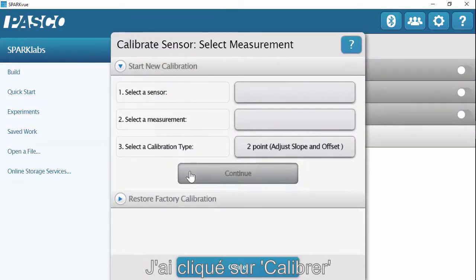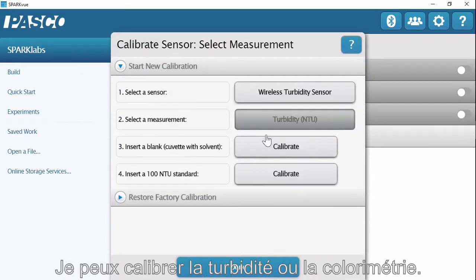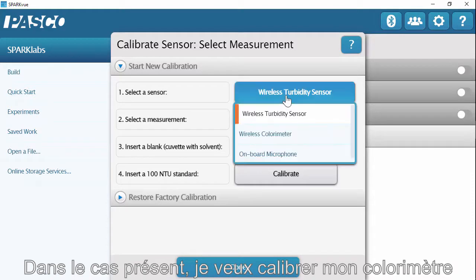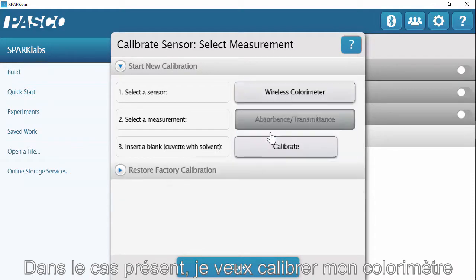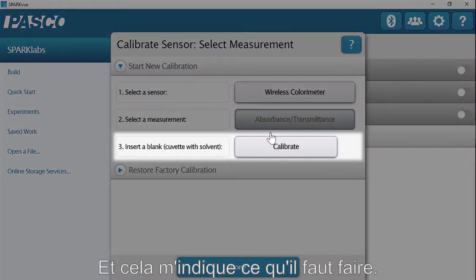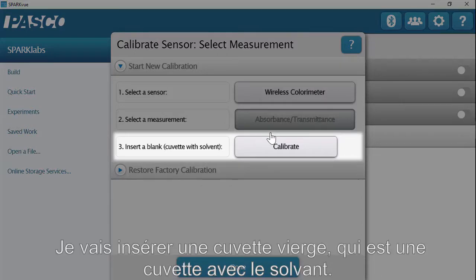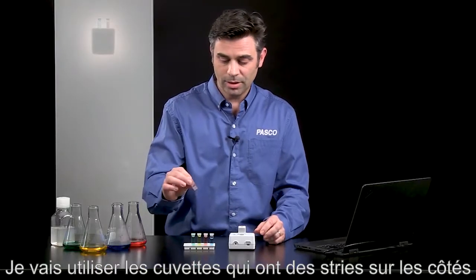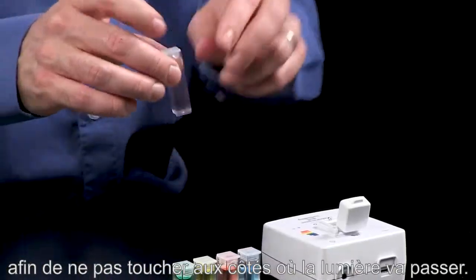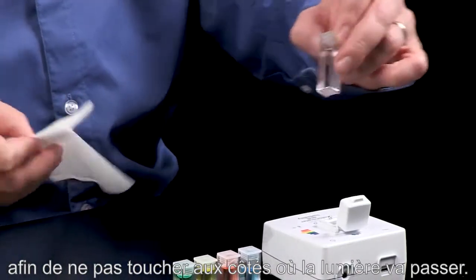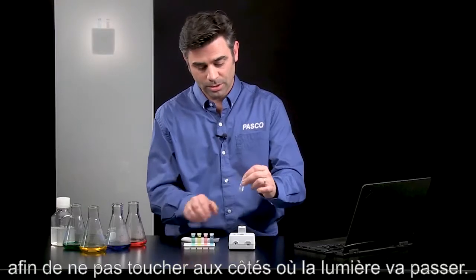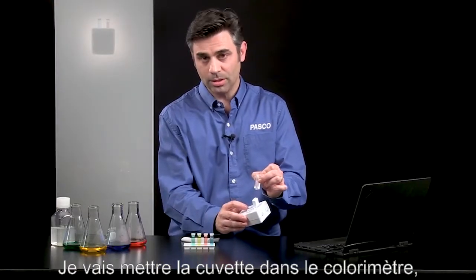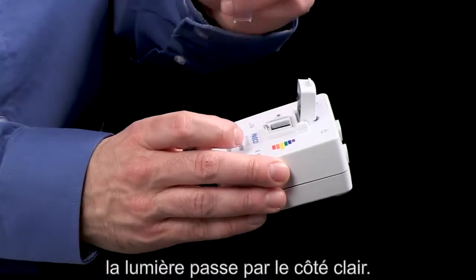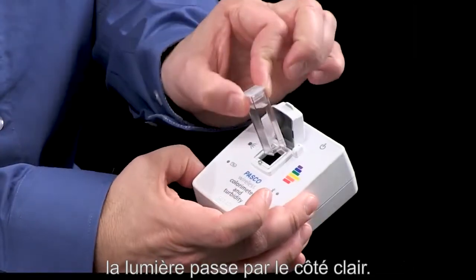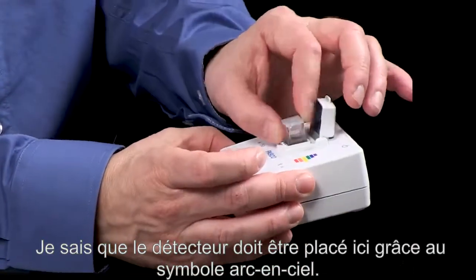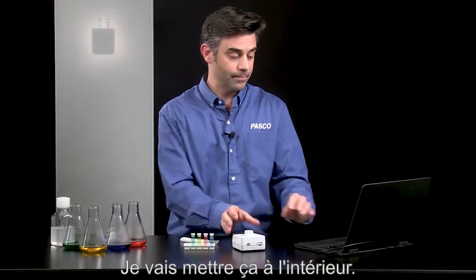So I hit calibrate, and I can calibrate either turbidity or colorimetry. In this case, I want to calibrate my colorimeter. And it instructs me about what to do. So I'm going to insert a blank cuvette, which is a cuvette with a solvent. I'm going to use the cuvettes that have ridges on the sides so that I don't touch the cuvette where the light is going to go through. I'm going to put that into the colorimeter so the light goes through the clear side over to the detector. And I know that the detector is over here because of the rainbow. I'm going to put that in.